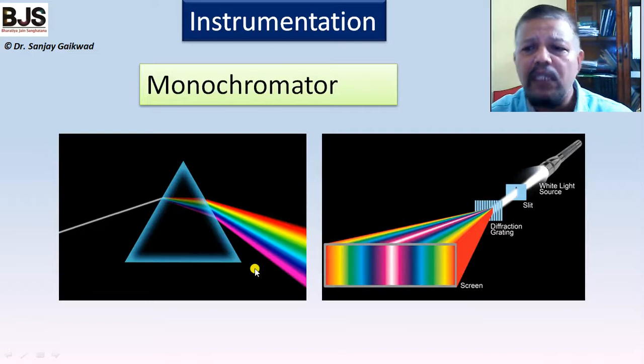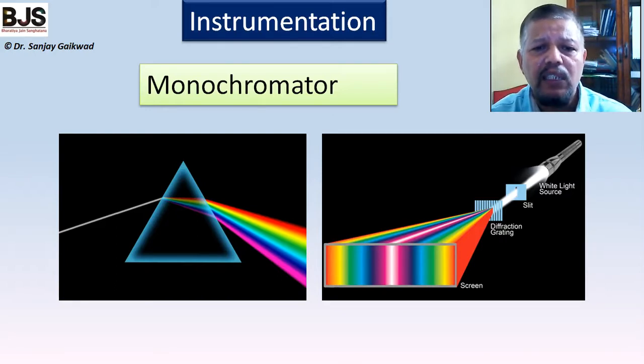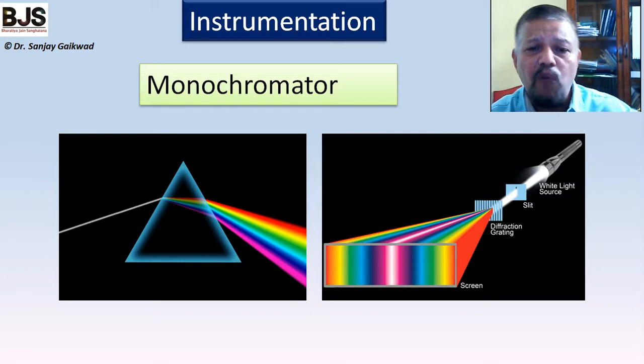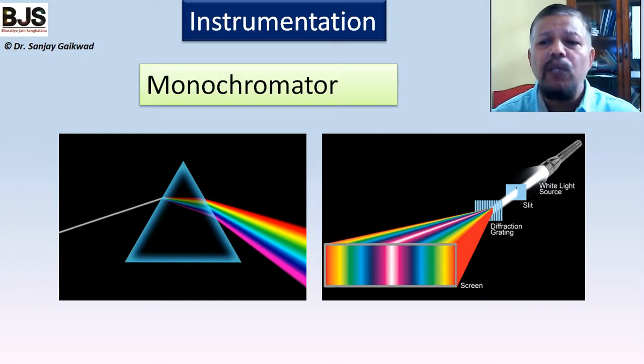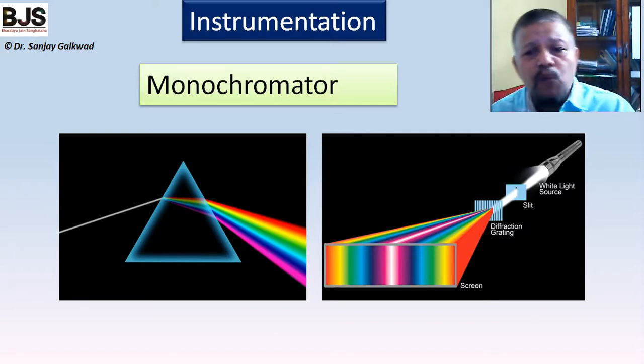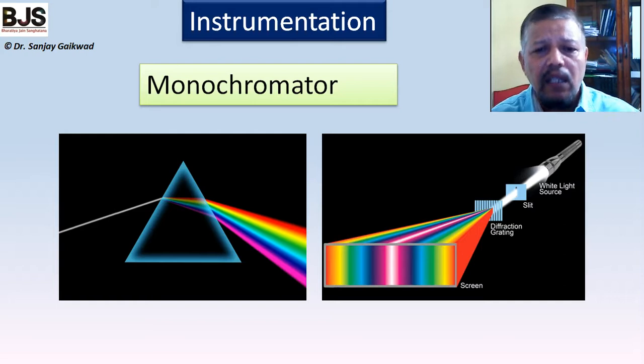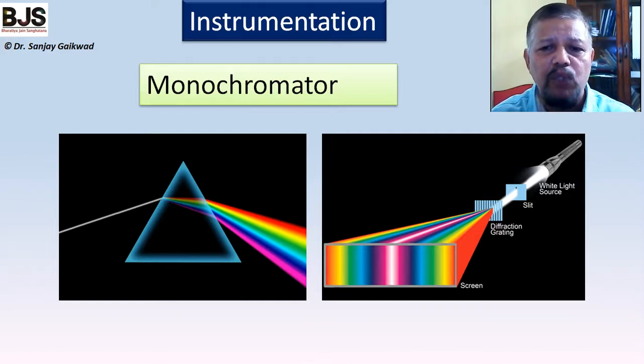The monochromator — either a prism or a grating — is placed after the flame. At high temperatures, metals other than the target element may also reach excited states and emit radiation back toward the detector. The monochromator acts as a filter, selecting only the radiation coming from the source, not the radiation emitted by the flame, ensuring accurate measurement.